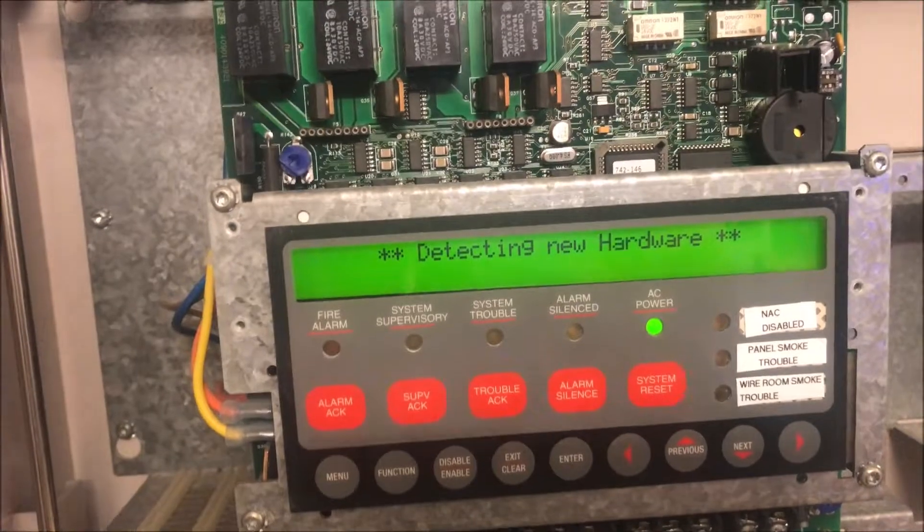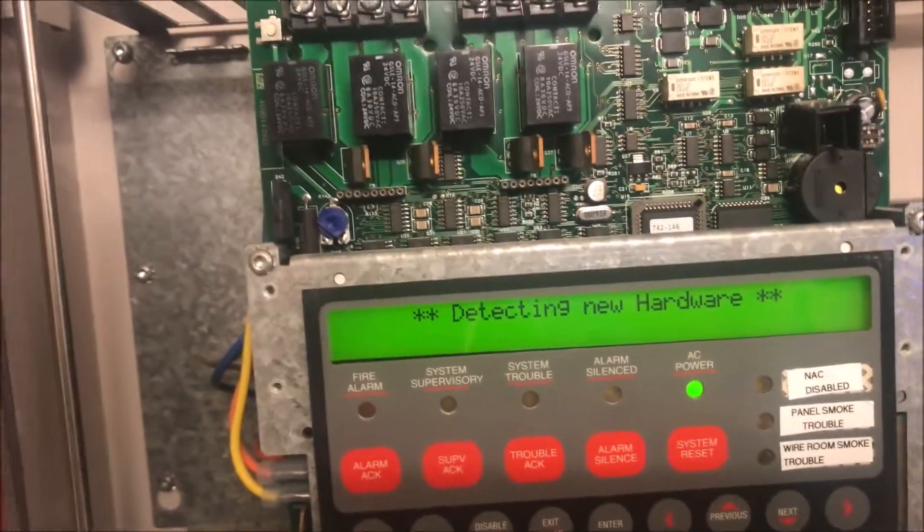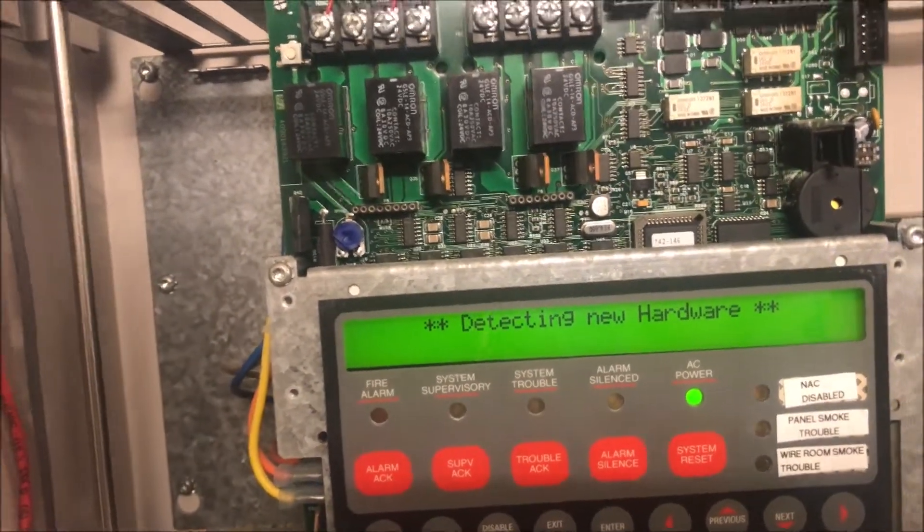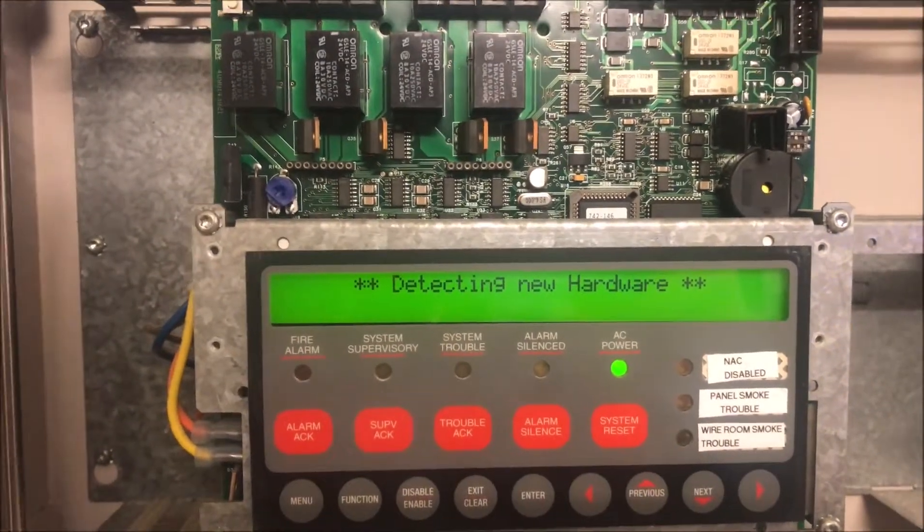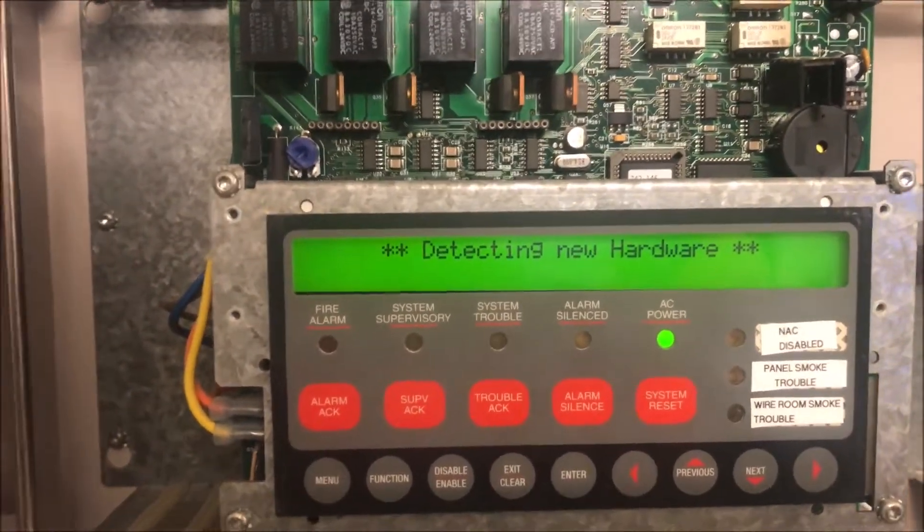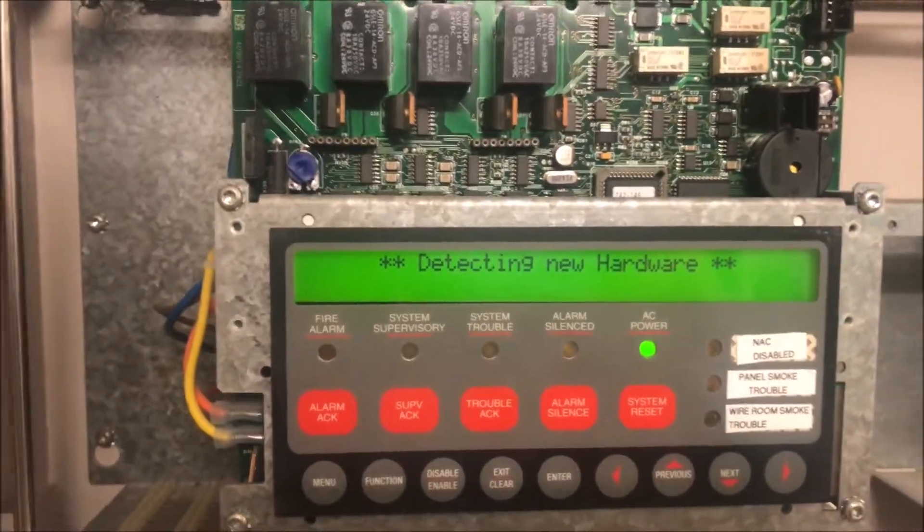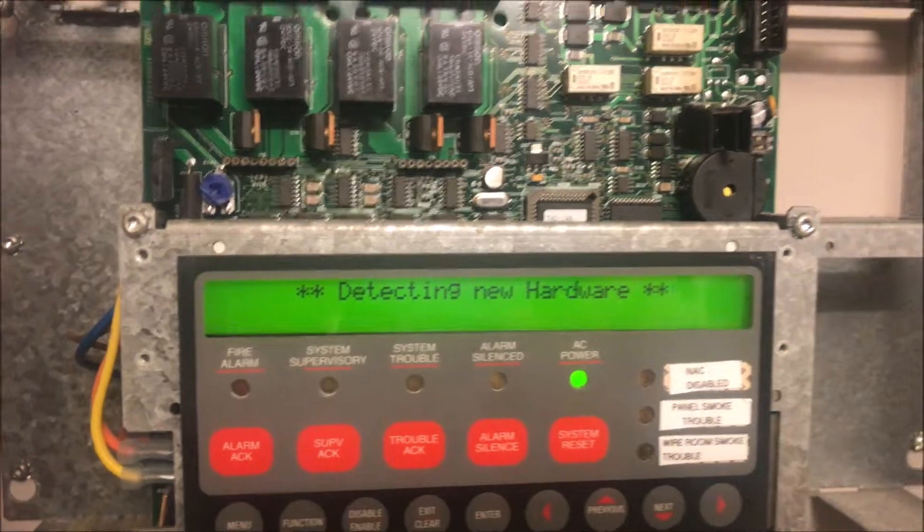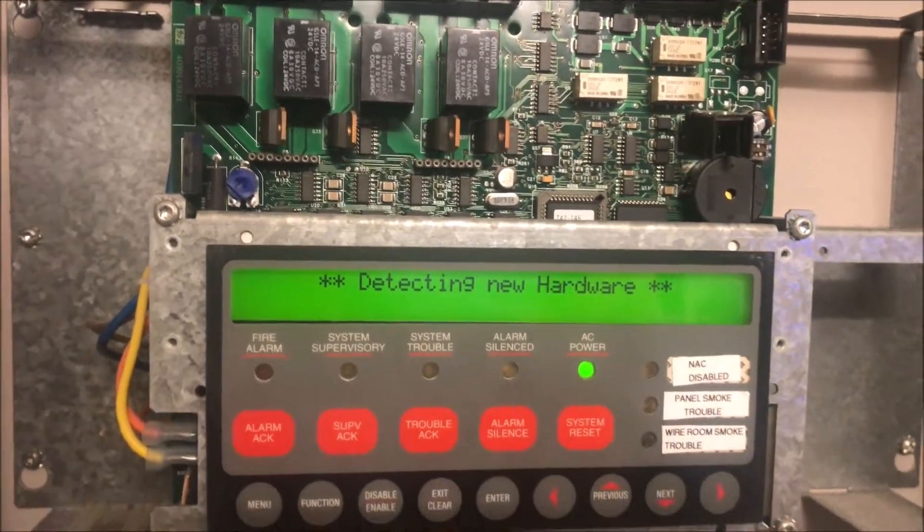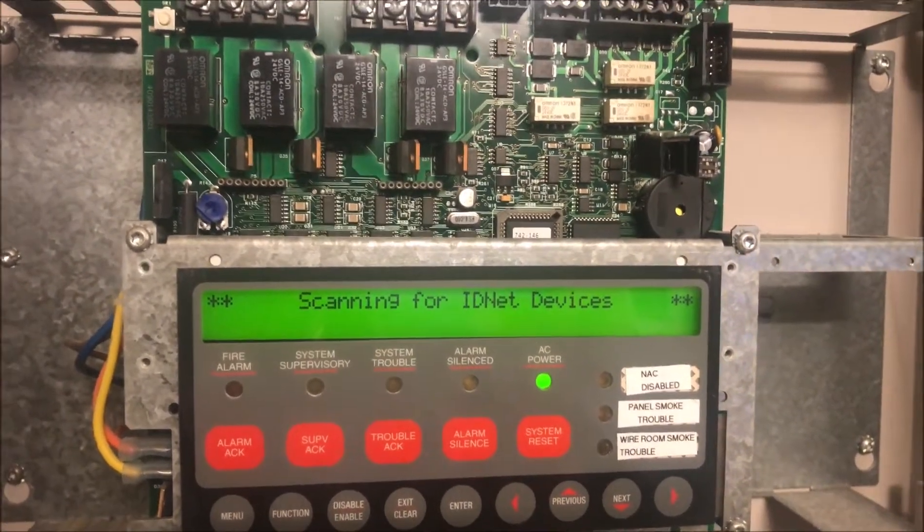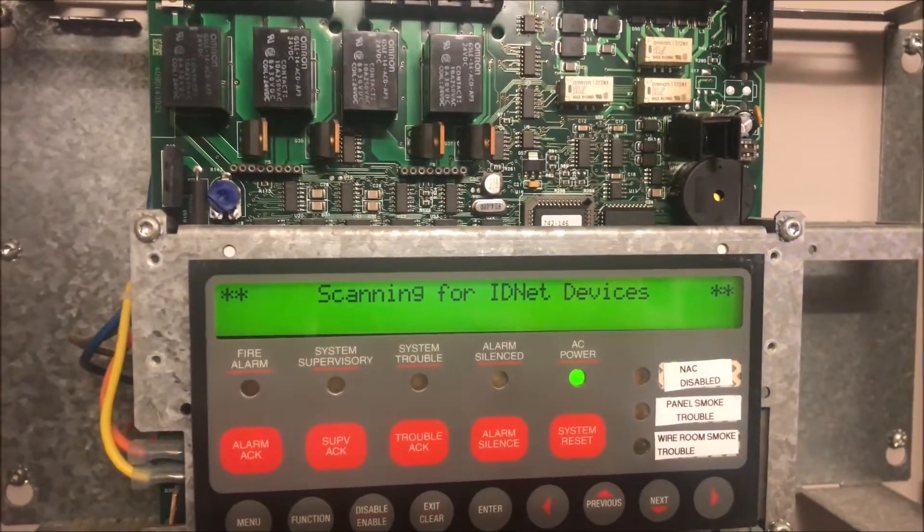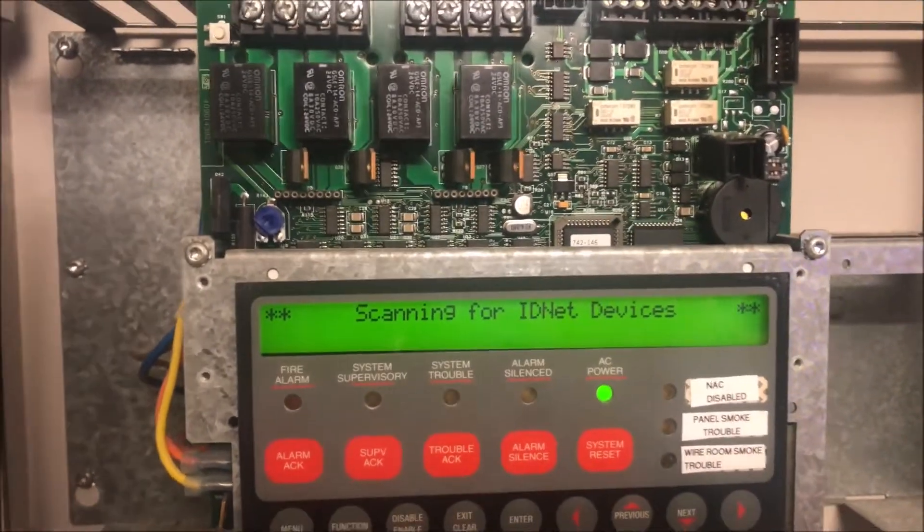It's going to go through its detecting stage. You will hear the 4010 polling chirp - it will sound a little different than the normal polling pulse as it is polling for the new card. You'll hear it click and change. Right now it is looking for anything - basically new cards. Now we are on to new IDnet devices.